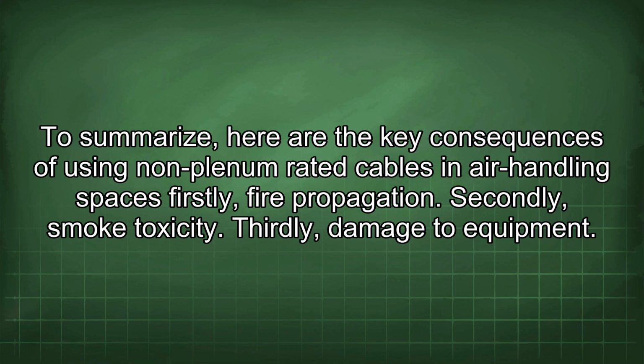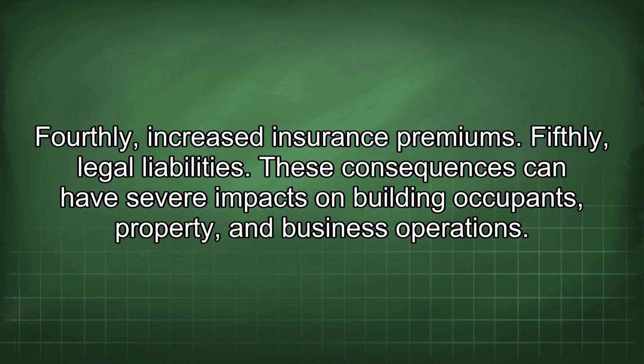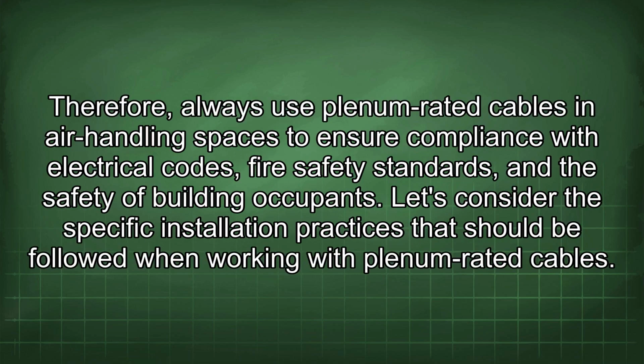Firstly, fire propagation. Secondly, smoke toxicity. Thirdly, damage to equipment. Fourthly, increased insurance premiums. Fifthly, legal liabilities. These consequences can have severe impacts on building occupants' property and business operations. Therefore, always use plenum-rated cables in air handling spaces to ensure compliance with electrical codes, fire safety standards, and the safety of building occupants. Let's consider the specific installation practices that should be followed when working with plenum-rated cables.